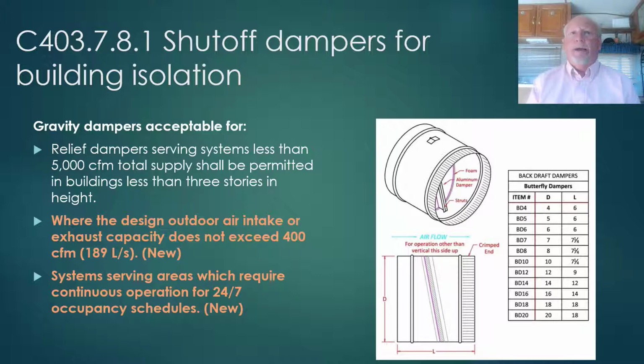So now you can apply gravity dampers to small air systems, including DOAS systems or ERVs or HRVs. And then also you can use gravity dampers for systems serving areas which require continuous operation on 24/7 schedules. So some new things there that will give some relief on having to provide motorized dampers on small air systems.